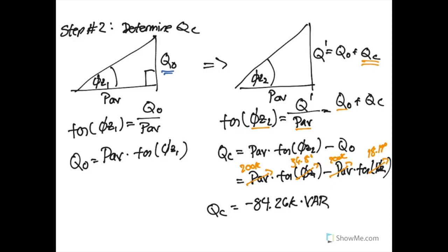Remember, reactive power is measured in VARs. Now we know how much the capacitor needs to contribute, and we simply need to size the capacitor so that when inserted into the circuit, it provides that amount of reactive power.